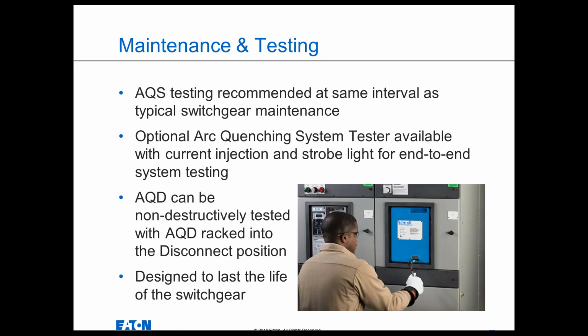So in terms of maintenance and testing on the system, we're not asking that you perform additional maintenance intervals, but whenever maintenance is performed on the switchgear, it could be a good time to do some testing on the Arc Quenching system. So whether you maintain your switchgear yearly, every 3 years or every 5 years, depending on the kind of environment the switchgear is operating in, that also is a good time to test the system.